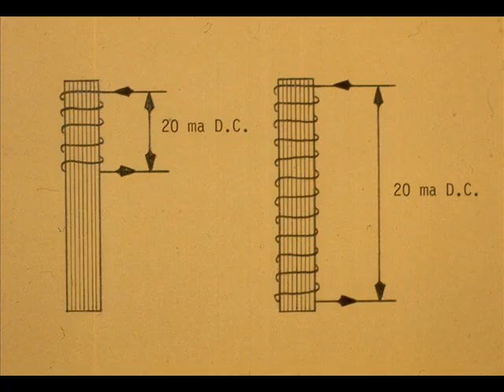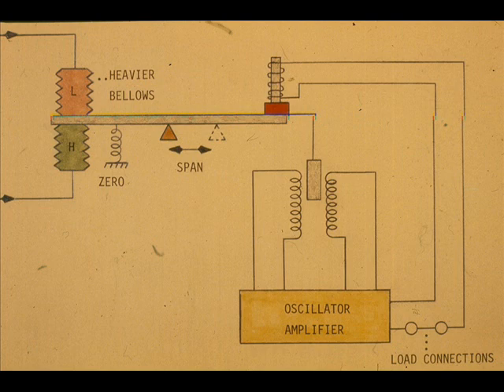An increase in the number of turns increases the feedback motor force for a given current. Range changes that cannot be achieved with the zero and span adjustments require a stronger measuring device and an increase in the number of turns, whether it is a bellows, diaphragm, or capsule.